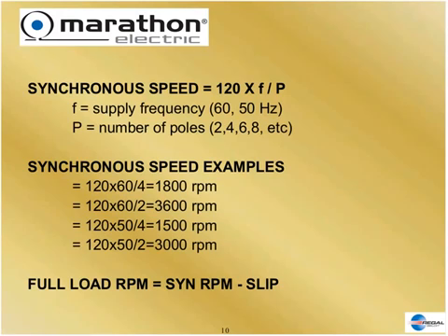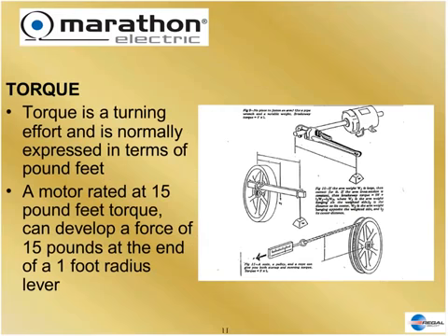There are two speeds to discuss with motors. Synchronous speed is the speed of the wave. Motor speed — the actual shaft speed — is different from synchronous speed by a factor called slip. The motor speed is always less than synchronous speed. Why? Because the shaft is always being held back by a concept called torque. When the motor is producing torque and the load is demanding torque, those two will meet and balance at a speed slightly less than synchronous speed — that's where slip comes in.